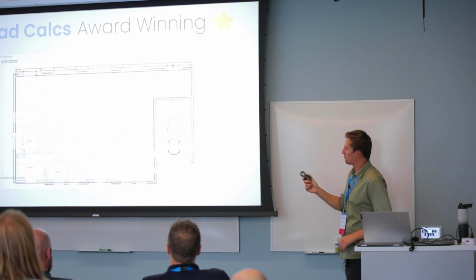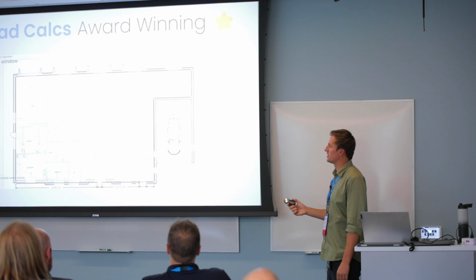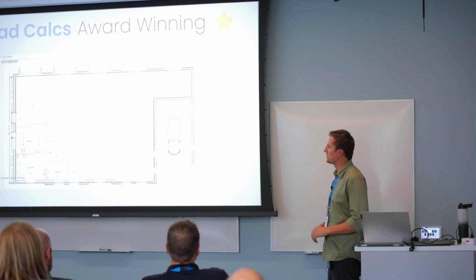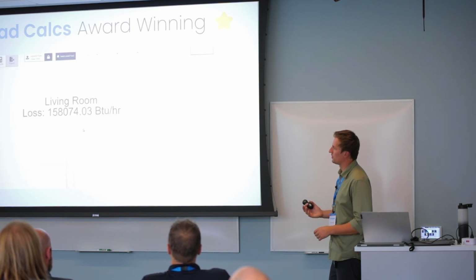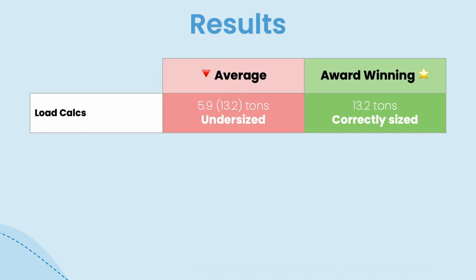Just to finish this off, when we zoom in, the total heat load is 158,000 BTUs, I think, just more. So if we do a quick comparison after the first step of the load calculations, it's pretty easy to see, with the colors as well, that for the average designer they've found a 5.9 ton heat pump will be sufficient, but in reality that's massively undersized. We've just realized it needs to be 13.2 tons, but they don't know that, and they're never going to find out until they turn it on, which is way too late, and it's going to get worse, as we'll see.